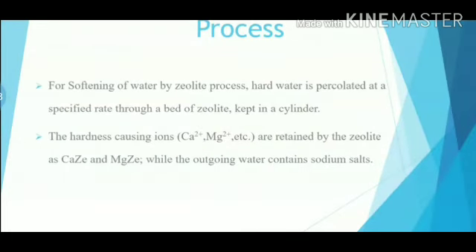Now, the process of zeolite. For softening of water by zeolite process, hard water is percolated at a specific rate through a bed of zeolite kept in a cylinder. The hardness-causing ions are retained by the zeolite as calcium zeolite and magnesium zeolite, while the outgoing water contains sodium salts.